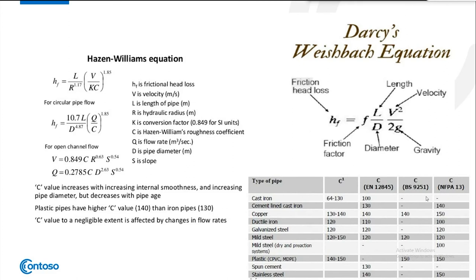The equation is HF equal to (L over R) raised to 1.17, multiplied by (V over KC) raised to 1.85. The formula for circular pipe flow is HF equal to 10.7L over (D raised to 4.87), multiplied by (Q over C) raised to 1.85.